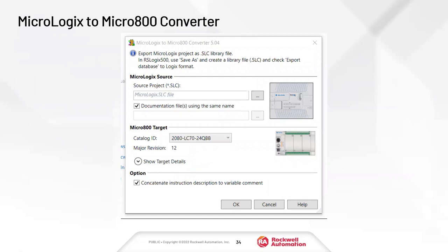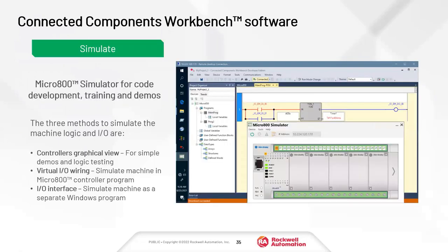There is a MicroLogix to Micro 800 converter built into CCW — you can import your MicroLogix program right into CCW. Another unique feature is the built-in simulator at no additional cost. You can create a project, write some code, fire up the Micro 800 simulator, connect to it, and test your logic. The simulator shows a virtual Micro 850 where you can click inputs to toggle them on and off and watch outputs light up.